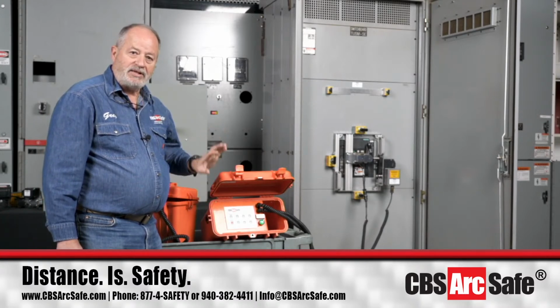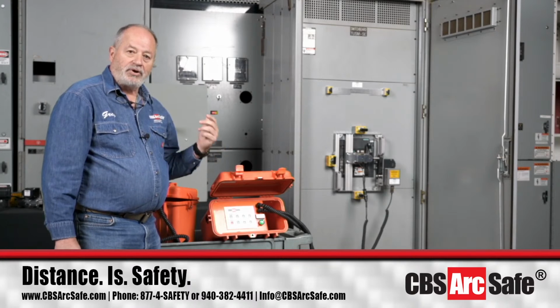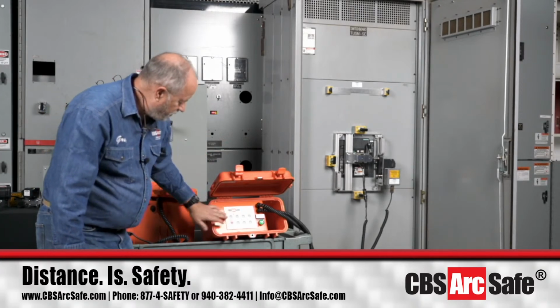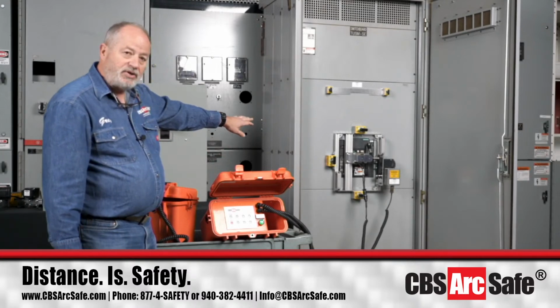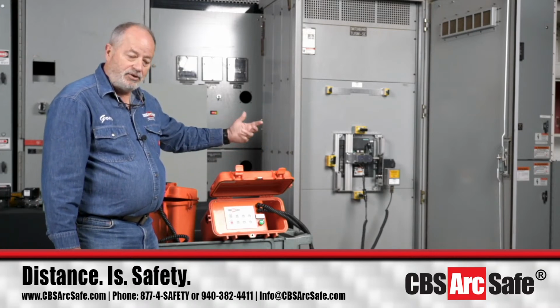And so that's why that's labeled charge, close. Close and trip are simply for the two buttons on the face of the breaker for closing and tripping the breaker, if that's how the breaker is configured. So we only have to touch this once and it's going to count our strokes for us. We can check the indicating gauge on the face of the breaker to see that the spring is charged at the end of that. And then we can hit the close button and the trip button.